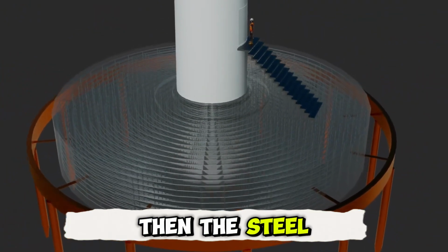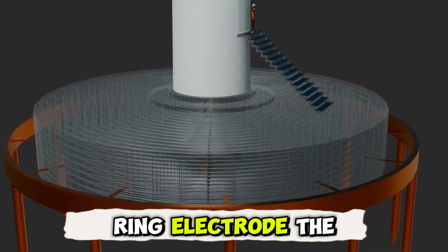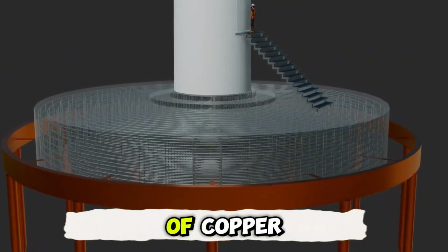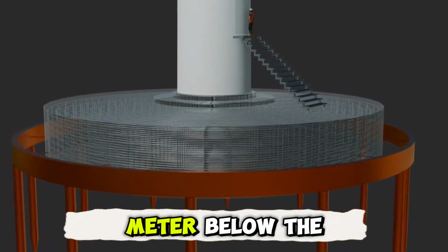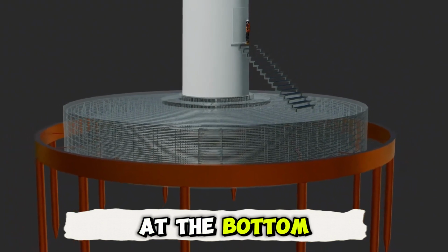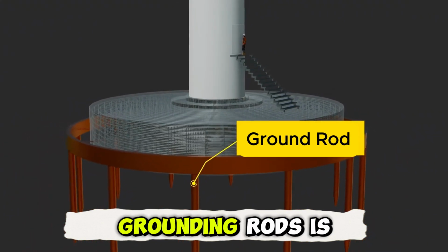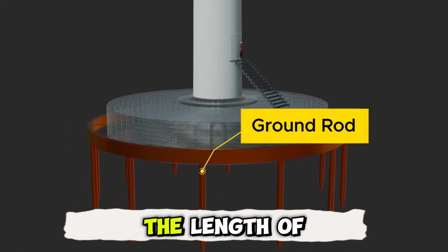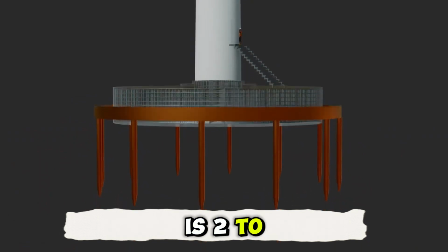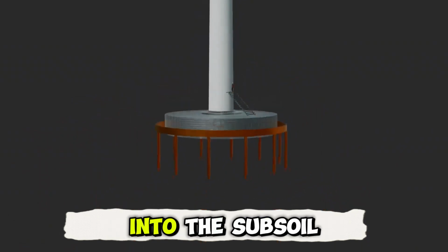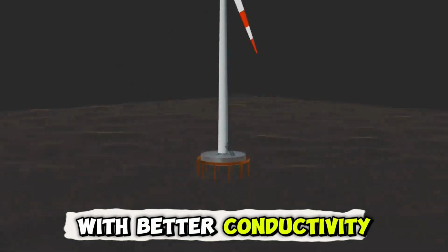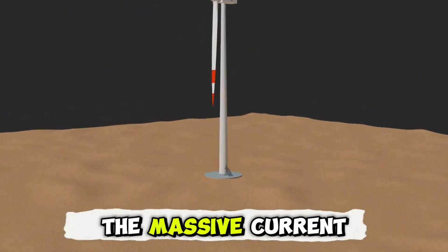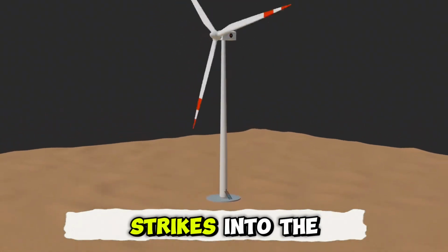Then, the steel frame is connected to the outer ring electrode. The electrode is made of copper, usually buried 1 meter below the ground. At the bottom of the ring electrode, a circle of grounding rods is also connected. The length of the grounding rods is 2 to 4 meters. They are driven into the subsoil with better conductivity to effectively direct the massive current generated by lightning strikes into the ground.